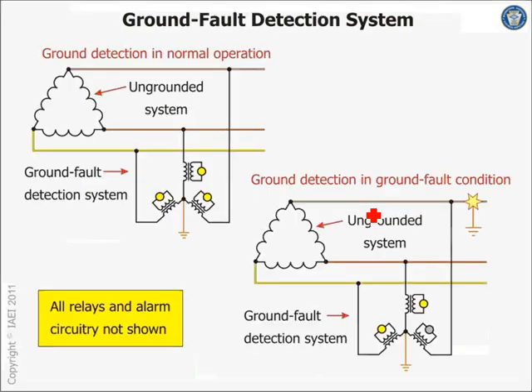Here's another, more advanced way, where you can use a transformer to reduce the voltage. And if you read this, all of it is an alarm circuit. Now, there is ground fault detection like the one you guys mentioned, where it can sense that you have a ground fault, sense how much current is going through the ground fault, and where the ground fault is located. It can locate the ground fault.